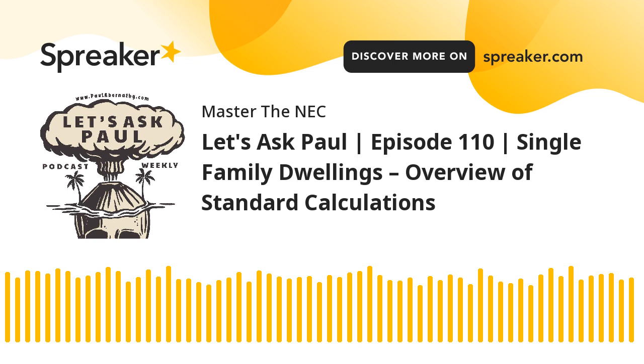Once we add all that up, we're simply going to divide that by the voltage from the supply, and that is probably 120/240. So we simply take whatever the total VA is, divide it by 240, and that's going to give us our minimum ampacity. And that's what we're going to be searching for conductors for. And we're going to go to 310.16, and we're going to try to find what size conductor we would use.